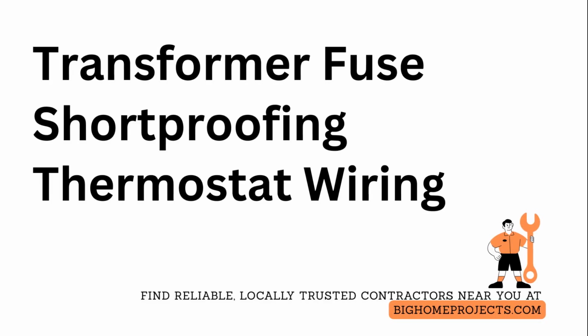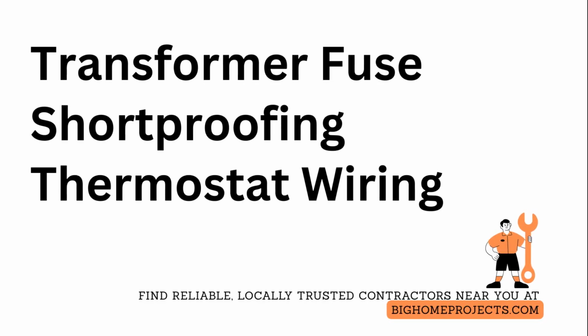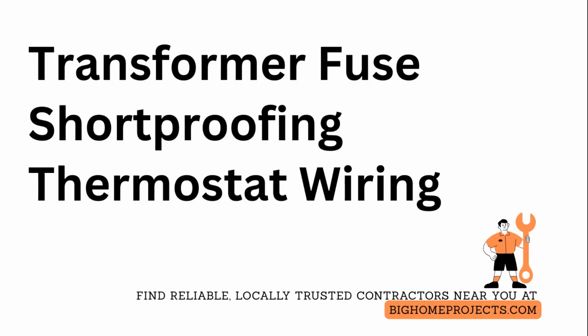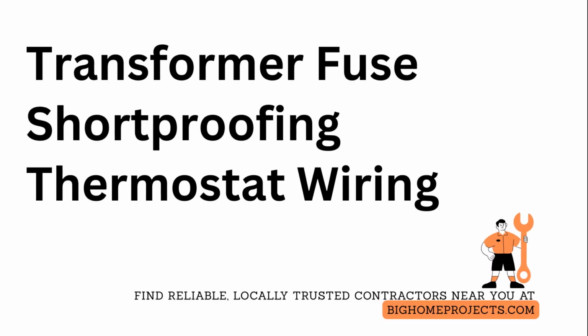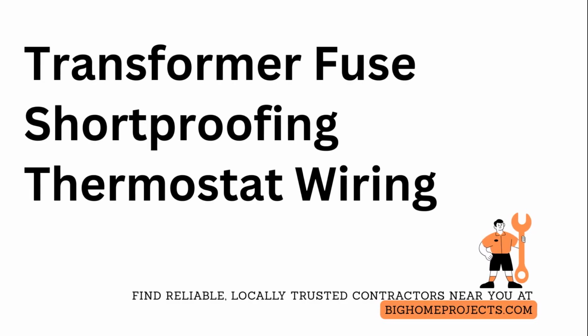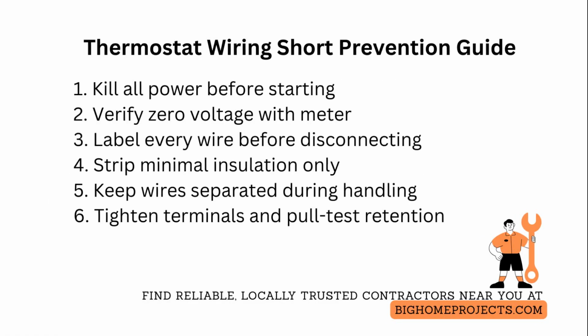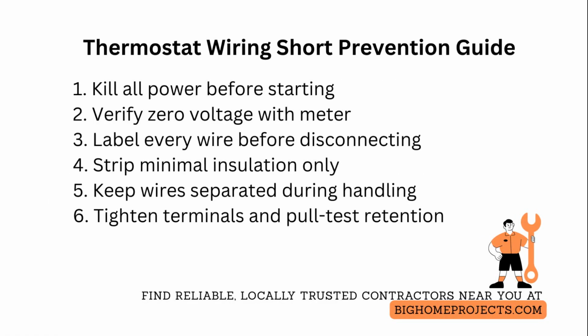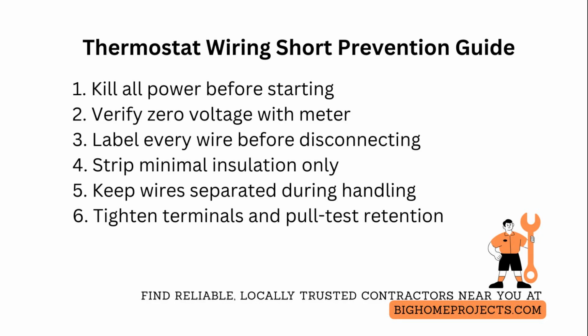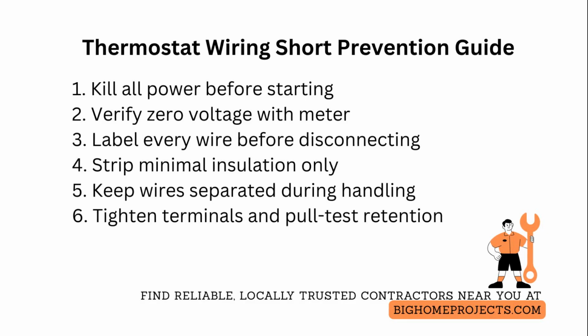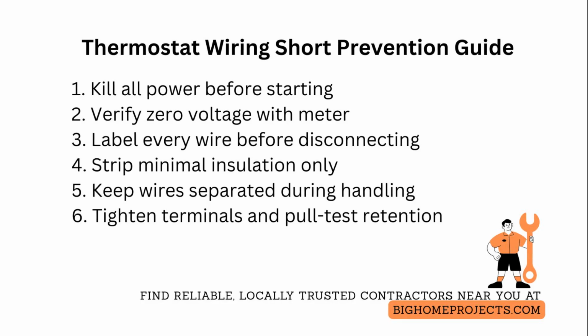Shorting the common and red thermostat wires during replacement can blow the furnace fuse, shut down control circuits, and leave the heating or cooling system dead until the fuse is replaced. Turn off the heating and cooling power at the breaker and confirm 0 voltage with a non-contact tester before you touch anything. Always treat the red conductor as live relative to the common and remove power completely to avoid blowing the control fuse. Expose the wire bundle gently.